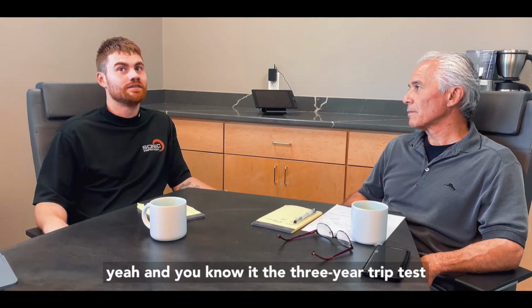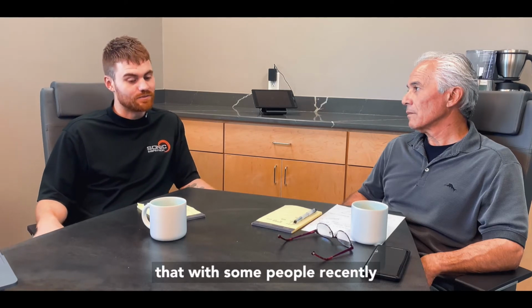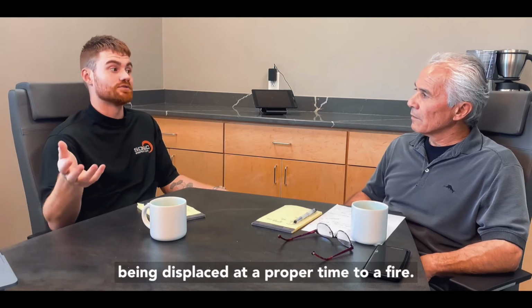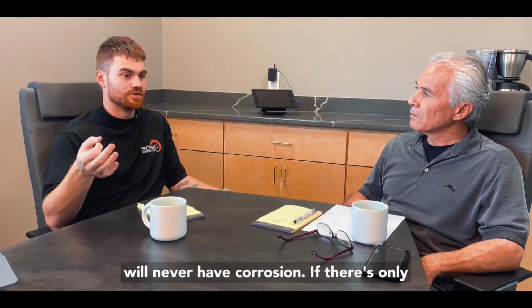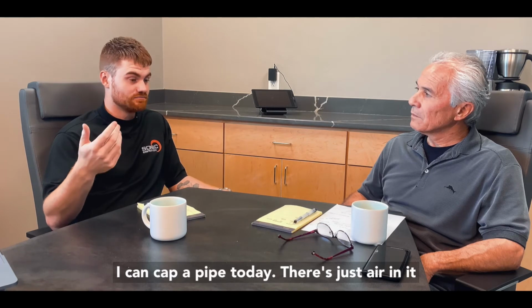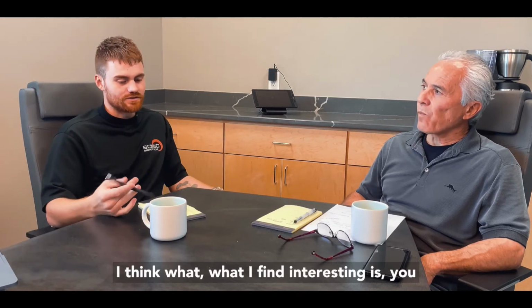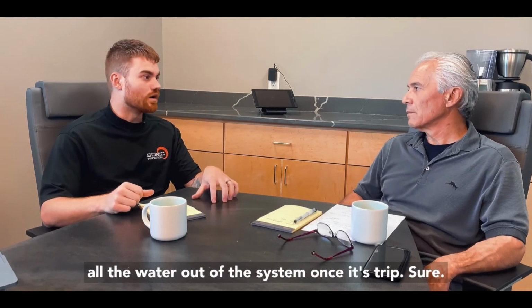Yeah, and the 3-year trip test, that's a hot topic. I had talked about that with some people recently, and there's lots of different views, because with the 3-year trip test we obviously want to make sure that the water is being displaced at a proper time to a fire. But for dry systems, a dry system will never have corrosion if there's only air or only nitrogen in it. You can show me, I can cap a pipe today, and there's just air in it. It's going to be good, right? Obviously, it's not a fire sprinkler system, but I believe that practice is leading to premature failures, because we're not getting all the water out of the system once it's tripped.